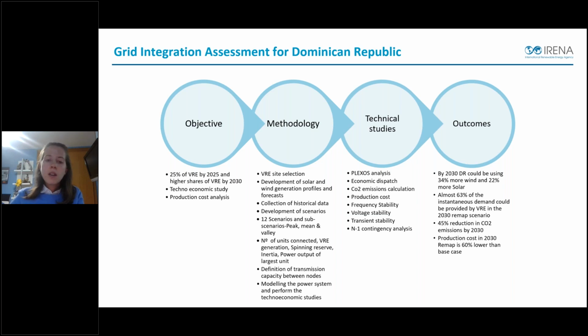The objective of the technical economic study was to assess the possibility of including 25% of variable renewable energy in the power system by 2025. The methodology of the study defined solar and wind generation profiles and forecasts. The collection of historical data was included, and the development of 12 scenarios and sub-scenarios was done, and also the power system was modeled. The technical studies performed were the Plexos analysis, the economic dispatch, the CO2 emissions calculation, production cost, frequency, voltage and transient stability analysis, and N-1 contingency analysis.